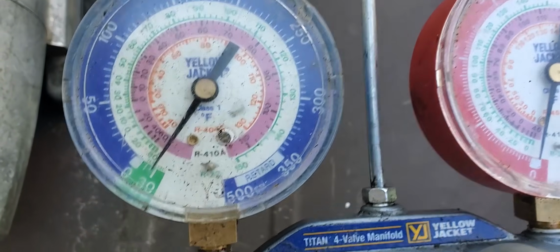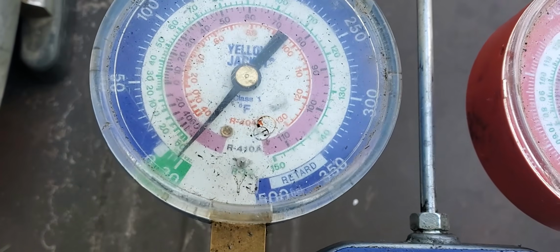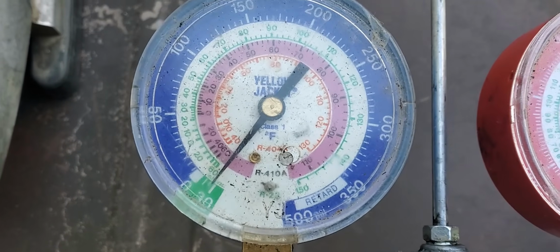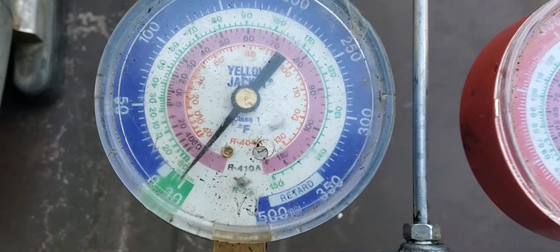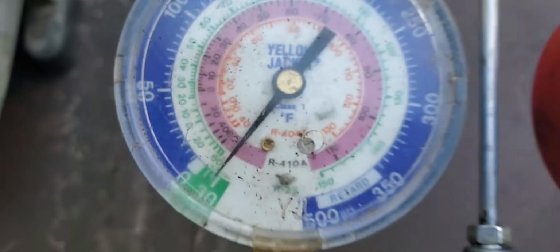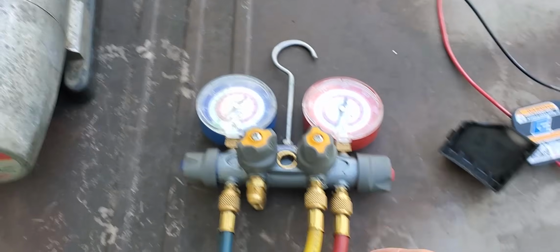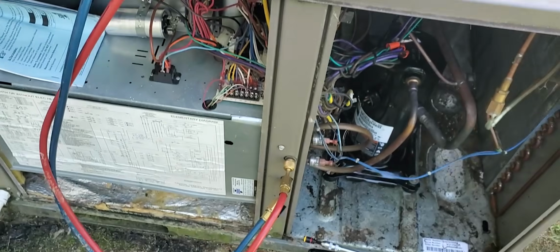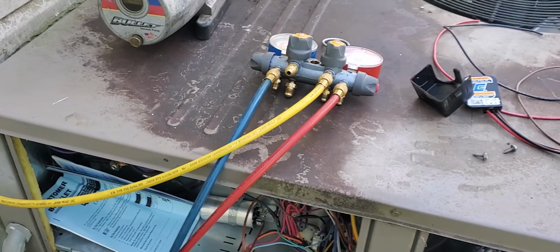If you see that it's in a vacuum, then it shouldn't move after you turn it off. If it starts to rise up, then you have a leak. So these are things you need to know in the field. You know how to hook your pump up, you need to have a good micron gauge.